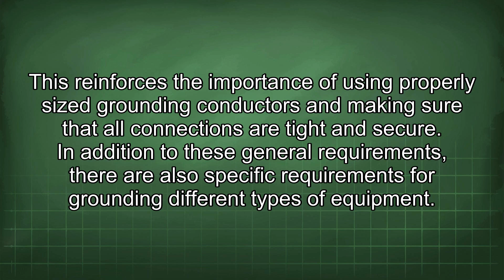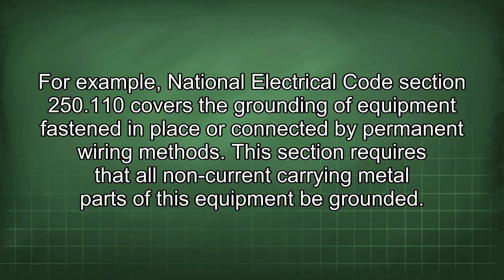In addition to these general requirements, there are also specific requirements for grounding different types of equipment. For example, National Electrical Code Section 250.110 covers the grounding of equipment fastened in place or connected by permanent wiring methods. This section requires that all non-current carrying metal parts of this equipment be grounded. This includes things like metal enclosures, motor frames, and other metallic parts that could become energized in the event of a fault.